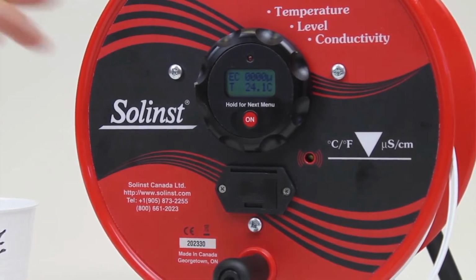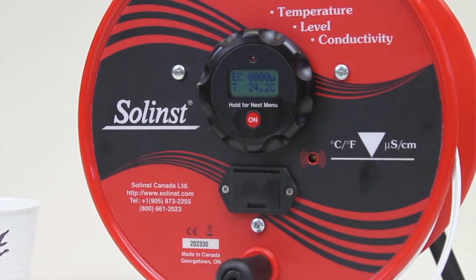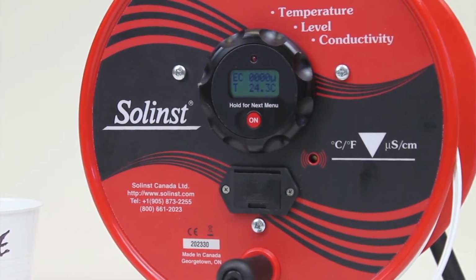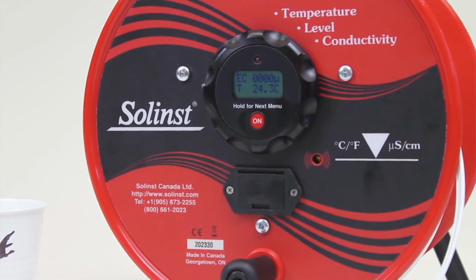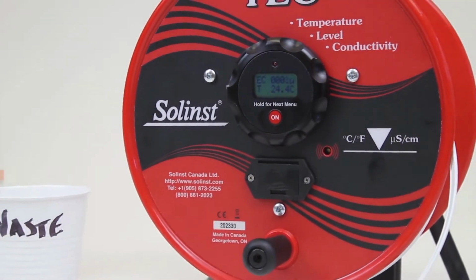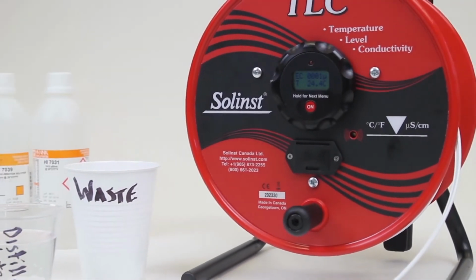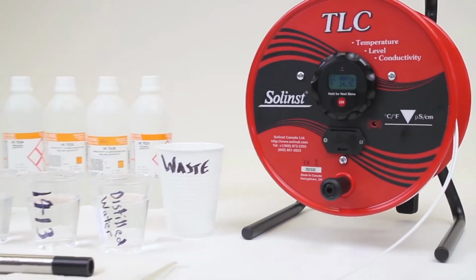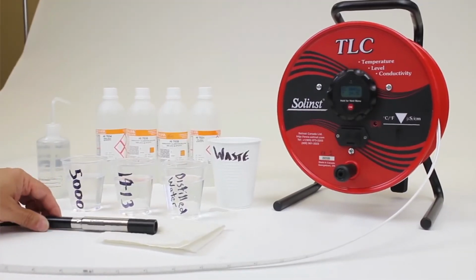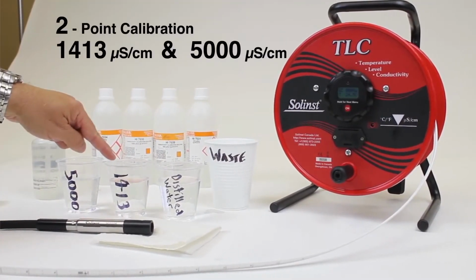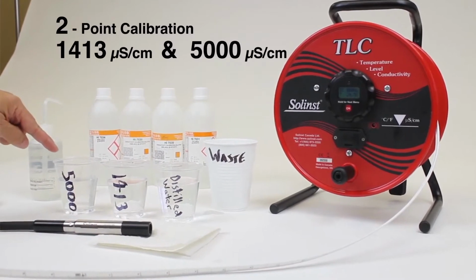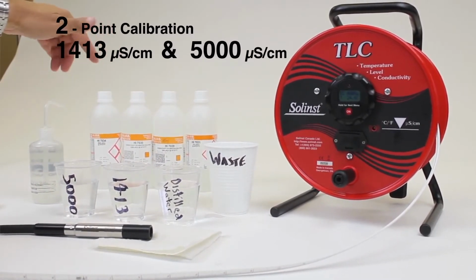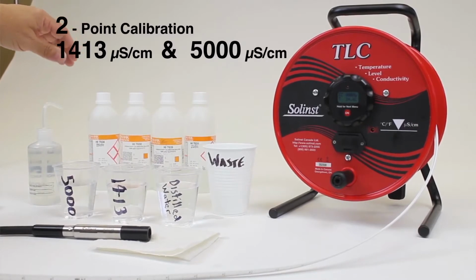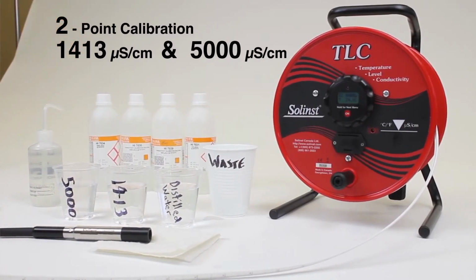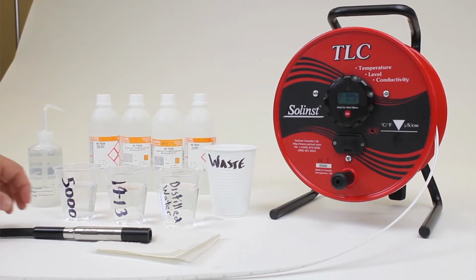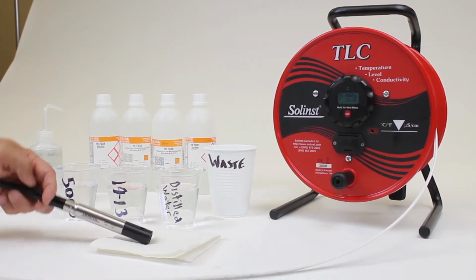If it wasn't, you would be looking at the temperature displayed, waiting for it to equilibrate with room temperature, and every time you put it into a new solution, also note your starting temperature and try and get to that temperature before you complete your calibration. So I'm going to calibrate at 2 points right now, 1413 microsiemens and then 5000 microsiemens. We also have some new bottles of 12,880 microsiemen and 80,000 microsiemen, so you can do a 1, 2, 3, or 4 point user calibration.